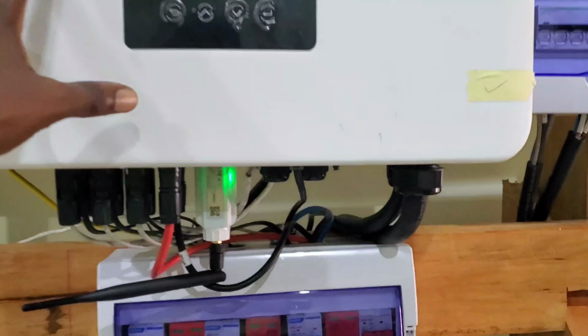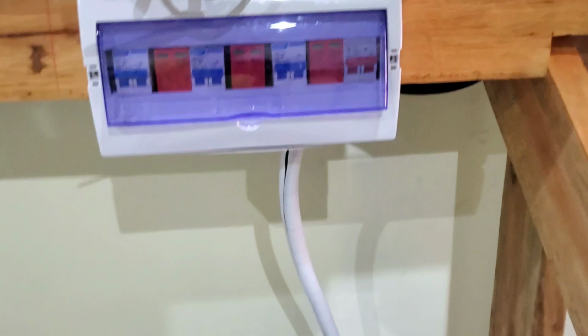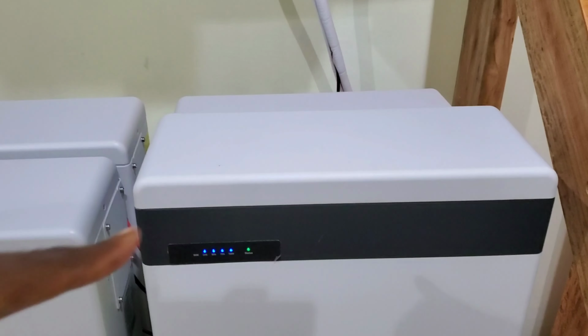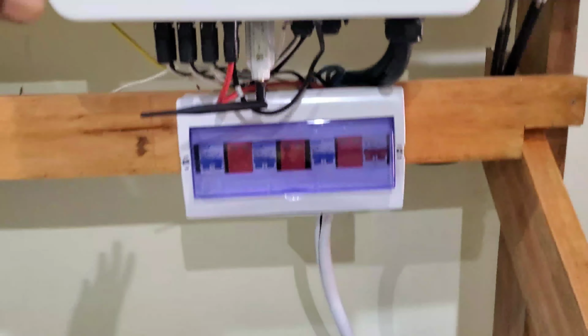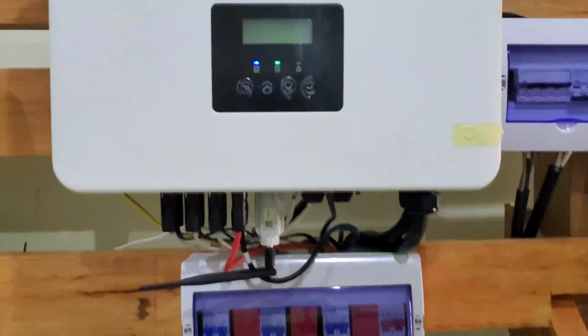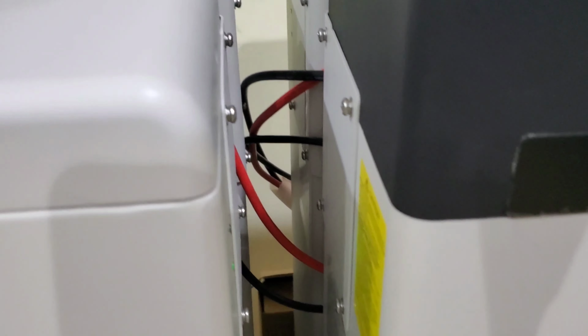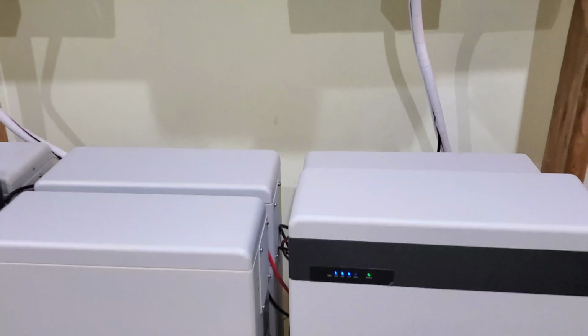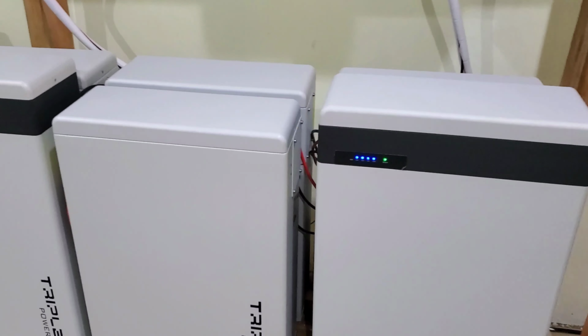Here, each inverter has 4 batteries, and the master battery has the BMS and it manages just those 4 batteries, nothing else. It communicates with this inverter. It's that simple, nothing else. But guess what the fun part is? Look at how thin our cables are. Okay, they're not worn. Do you know why we're able to get away with it? The reason we're able to get away with it is because we're running much higher voltages. So let me show you the voltage we're running on these 4 batteries.